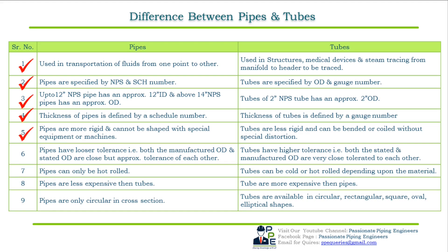Pipes are more rigid and cannot be shaped without special equipment or machines. On the other hand, tubes are less rigid and bending or coiling can be done without any special equipment. Pipes have looser tolerances — the manufactured and stated OD are close but approximate to each other. Pipes can only be hot rolled, whereas tubes can be cold and hot rolled depending upon the type of material.